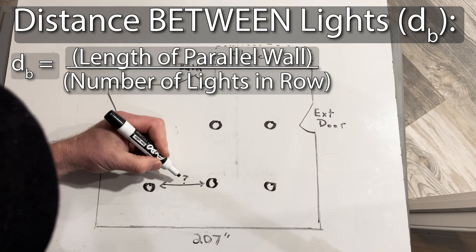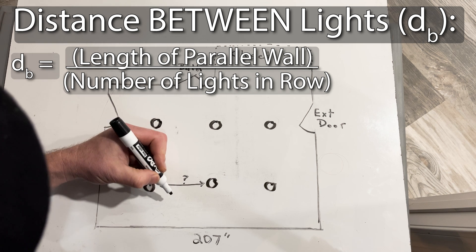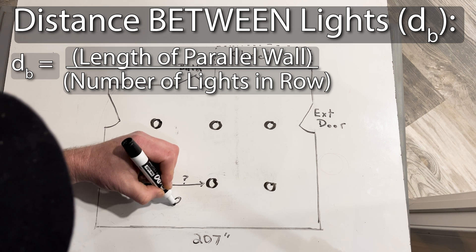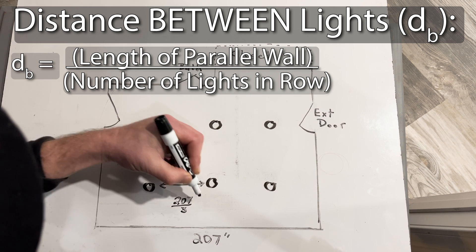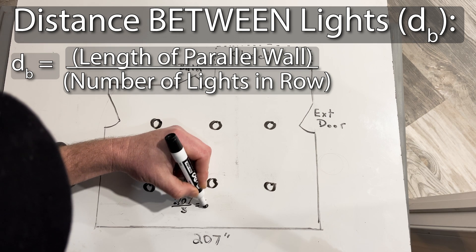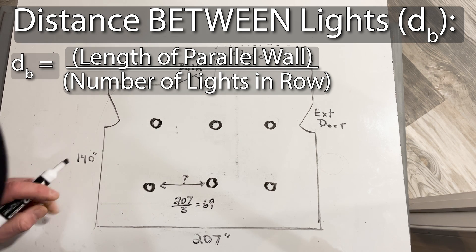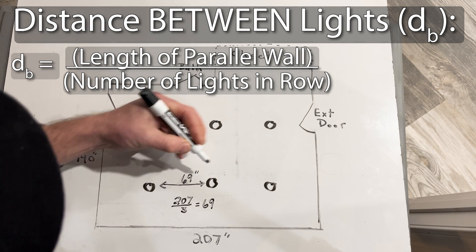For example, I've got three lights in a row parallel to the 207-inch wall. So I take the wall length, 207 inches, divided by the number of lights, three, which gives me 69 inches. So I'll have 69 inches between each pair of lights.